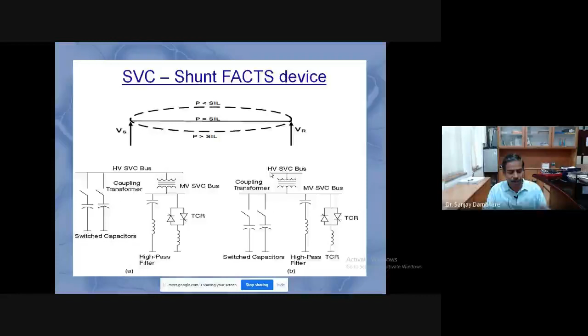If the line is loaded below the SIL, the line is subjected to over voltage, and if loaded above SIL, the line is subjected to under voltage. This happens because of the change in reactive power generated by the transmission line. With the SVC, we can absorb or give support to the reactive power of the transmission line, control the reactive power, and finally control the voltage.